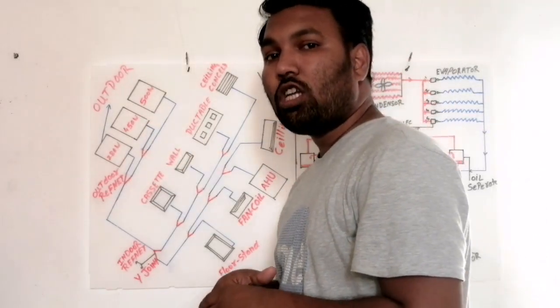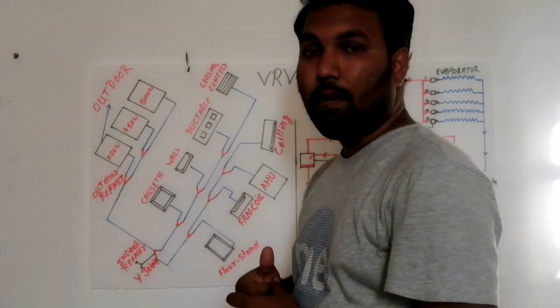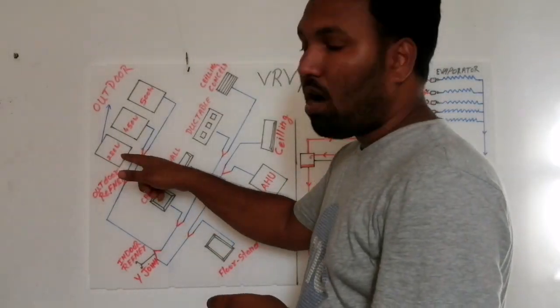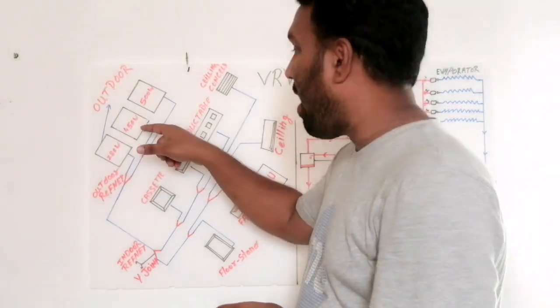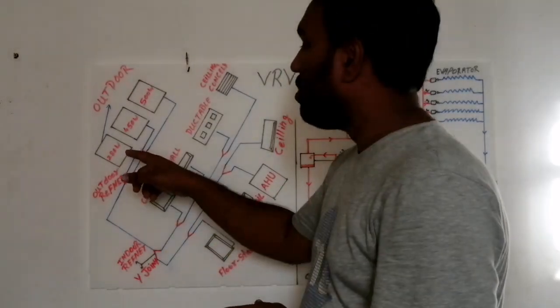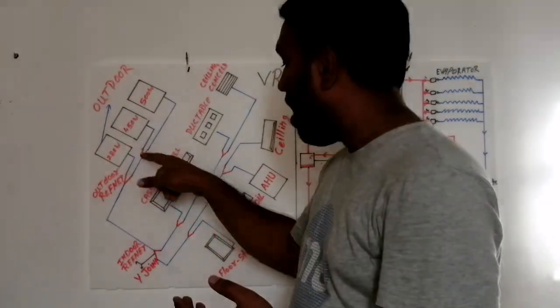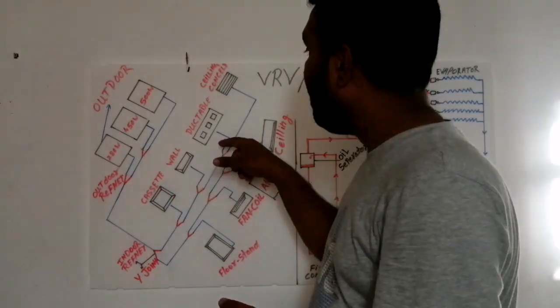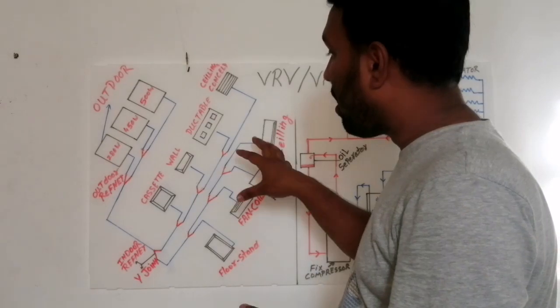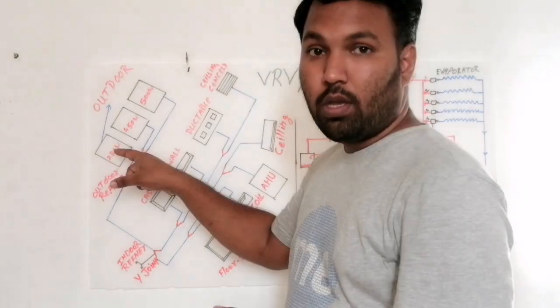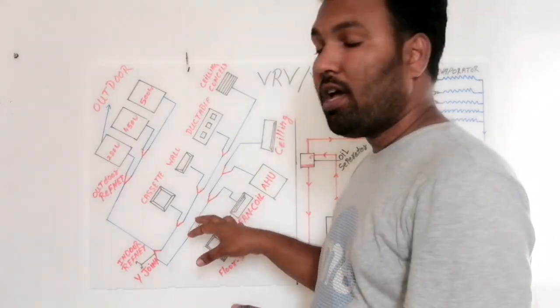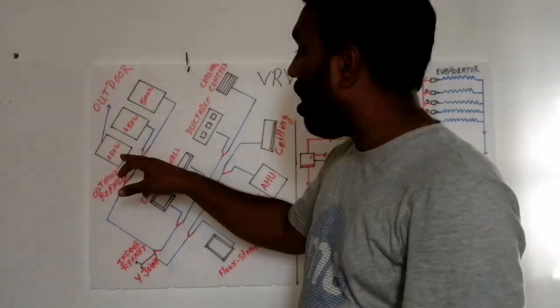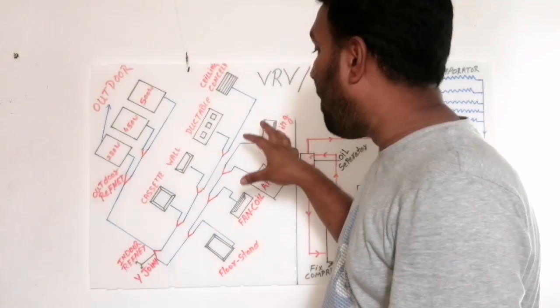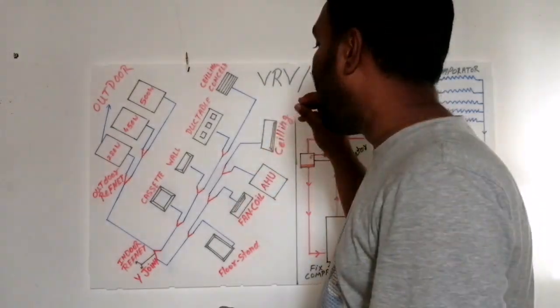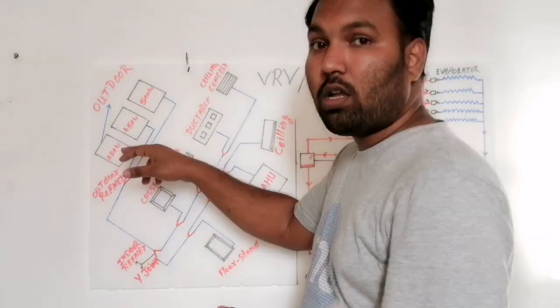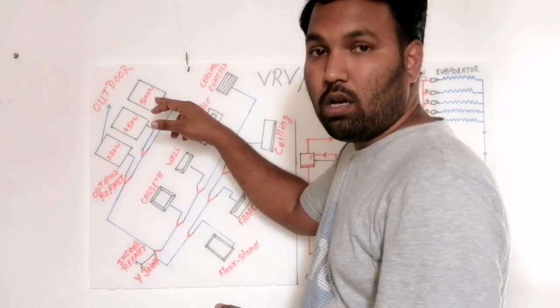If we talk about the communication cable between all the indoor and outdoor units, we can see it like this. Our first master outdoor is connected to slave 1, and slave 1 is connected to slave 2. From the master, one communication cable comes to our first indoor unit, and then we loop each of our indoor units over here. All the commands of the indoor units go to the master, because all the indoor units we have installed are controlled by only one outdoor unit, which controls them according to the capacity and cooling requirement of each indoor unit. At the same time, this master unit also controls the two slave compressors.